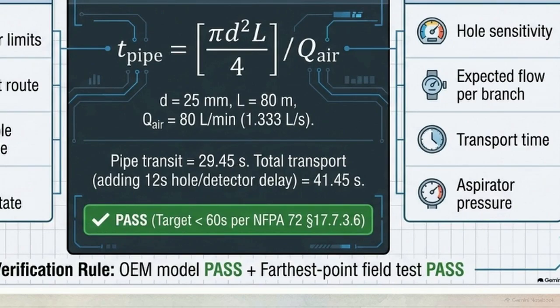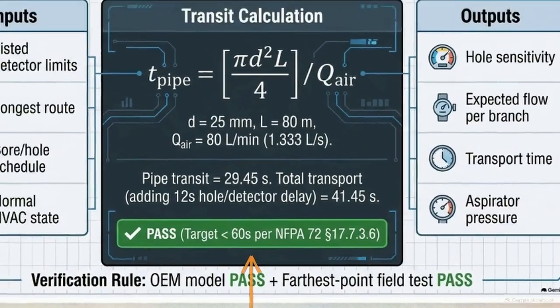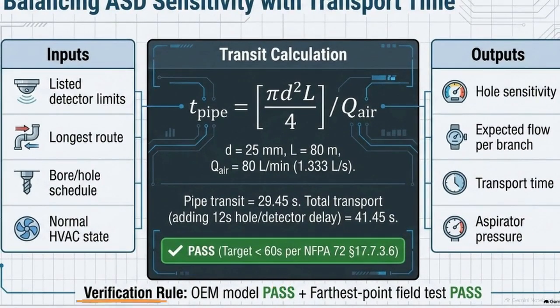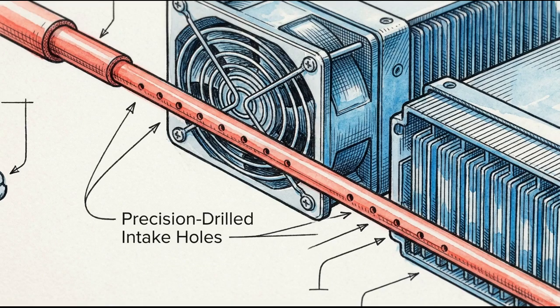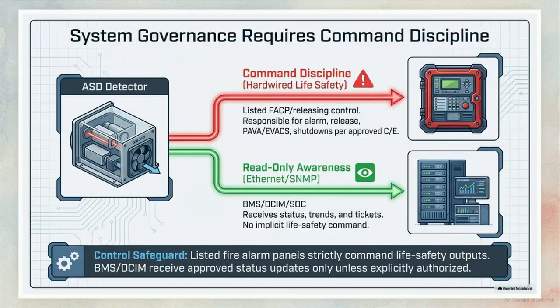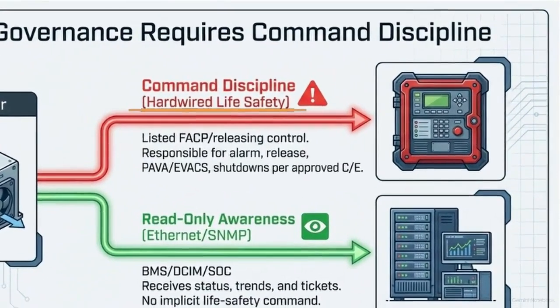limit required by NFPA. A software model passing the calculation is mandatory, but it's only half the requirement. The verification rule dictates that the software model must be proven by a physical, farthest point field test during commissioning. Relying on generic ceiling detection in high airflow environments invites failure. The physics of a data hall require bespoke, mathematically verified active sampling. Once that physical detection network captures a threat, we have to look at how the facility's digital brain processes the signal. This diagram shows the strict segregation required between life safety command and IT telemetry. A single ASD detector must feed 2 completely distinct systems. The top path is command discipline.